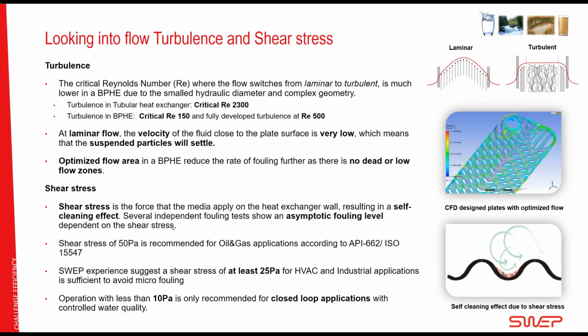And there are several independent fouling studies that I'm not going to show here because I don't have the time, but they show that there is an asymptotic fouling level, meaning that fouling starts and then evens out to steady state depending on the shear stress. So we know that with a high shear stress, we have a self-cleaning heat exchanger.